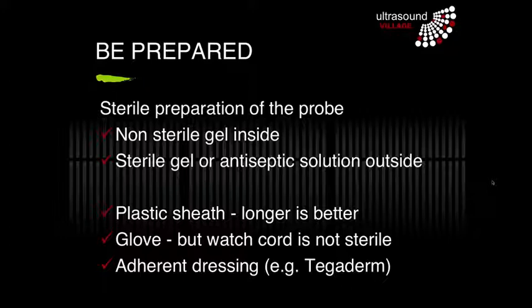The plastic sheaths, most departments should have these available now. If you're doing a fully sterile procedure, you need a long plastic sheath so that your cable is also covered and that doesn't disrupt your sterile field. You can use a sterile glove, but first of all, they're quite short, and secondly, the fingers tend to flop back and get in the way, and they've often got air in them. You can use an adherent dressing. That tends to work well, but if you're going to do that, make sure you put some gel over the end of the probe before you put the dressing over. Otherwise, when you take the dressing off, you might rip out the rubber cover that sits on top of all the crystals, and then you need to buy a new probe.